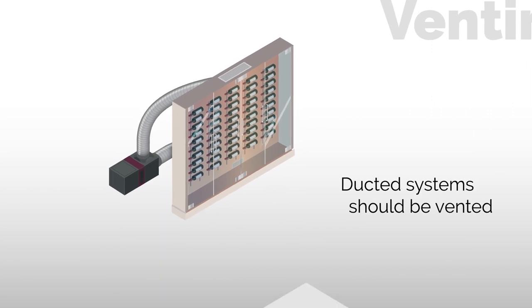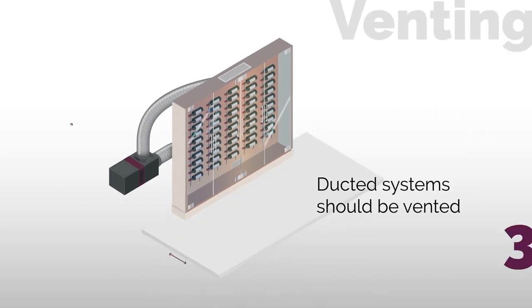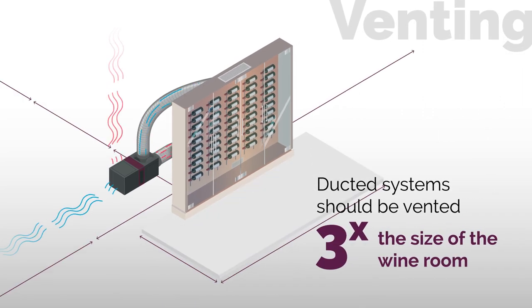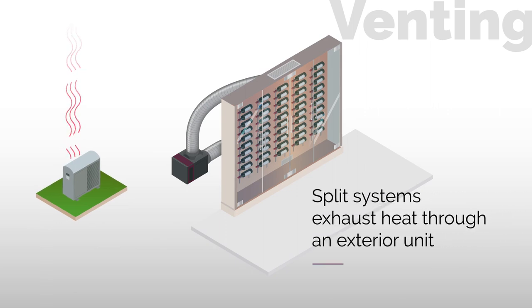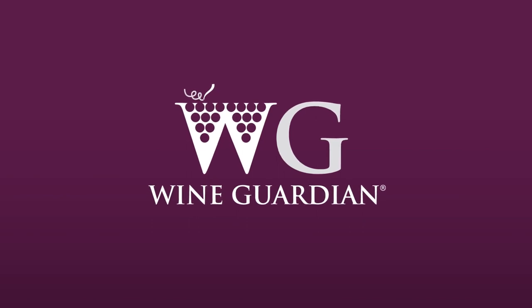Lastly, self-contained ducted systems should be vented to a space three times the size of the wine room, whereas split systems exhaust heat through an exterior condensing unit.